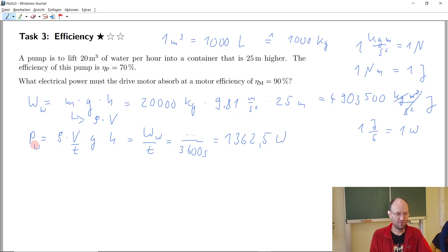So how to continue? That's the power that's needed to get the water up and now we need to divide by the efficiency of the pump and afterwards also divide by the efficiency of the motor. Exactly. So to get the power that goes into the pump, the power of water divided by the efficiency of the pump.